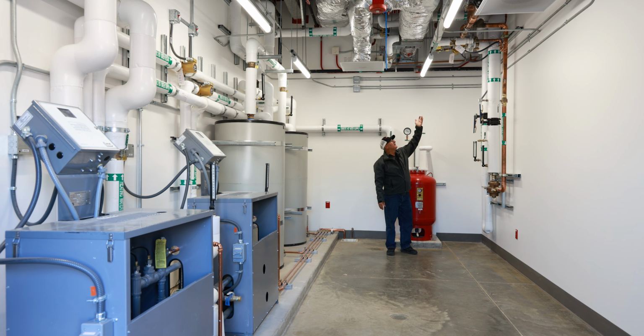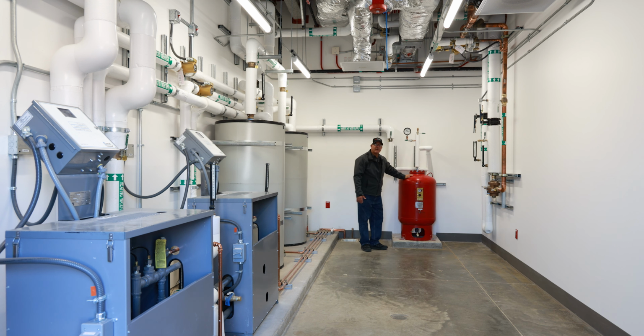Above the mixing valve are the two hot water recirc pumps. These are recircing hot water out to the building to the fixtures. Behind me is the expansion tank. Not much to say about this. It just sits here and provides expansion for the heating and cooling of the water.